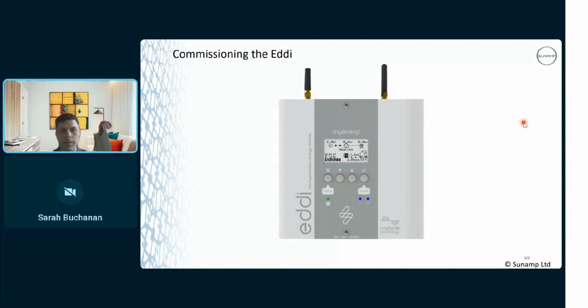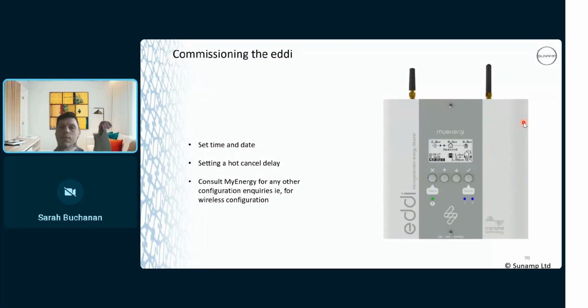So, commissioning of the eddi. There's only a few settings that we really need to be dealing with when it comes to the heat battery. So you set your time and date, and you set in a hot cancel delay as well. If you remember before when I was talking about that soft overheat, the element can cycle off and back on again until the heat starts to circulate within the battery. It'll stay on constantly. On its off cycle with an eddy, the eddy will come up with a maximum temperature reached display. What the hot cancel delay does is it ignores that message for up to an hour. So set it for 45 minutes for up to the 150. For the 210s and the 300, I'd set it to the maximum 60 minutes.